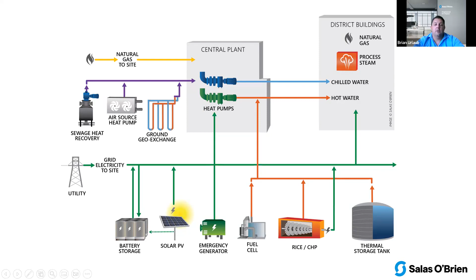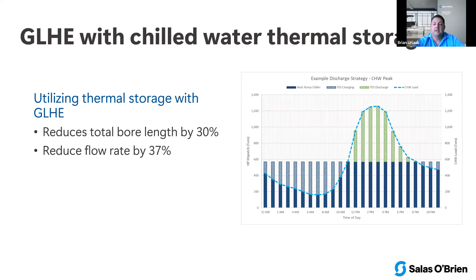One thing we've done recently on many projects like this is add thermal storage. Thermal storage has a huge impact, both from a rate structure perspective on peak charges and from reducing the ground loop, which is your largest capital expenditure when you're talking about thousands of boreholes for these campuses. Adding thermal storage flattens the load on our system, letting us reduce overall capacity and CapEx because we avoid that huge peak. Same thing applies with heating—that's two different tanks, not one tank being flipped; it's a hot tank and a cold tank.